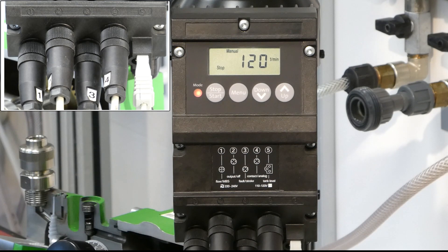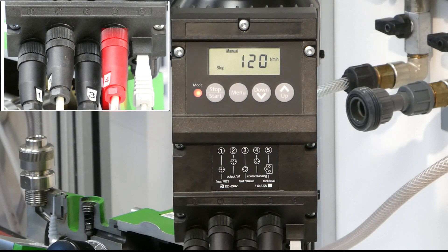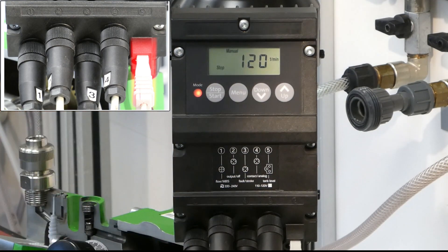On socket number four, you can connect external signals like an analog signal or a contact input coming, for example, from a water meter, typically. On socket number five, you have the possibility to connect the suction lance with the level switches, so that you can get a pre-empty signal or a finally empty signal, which can then stop the pump.